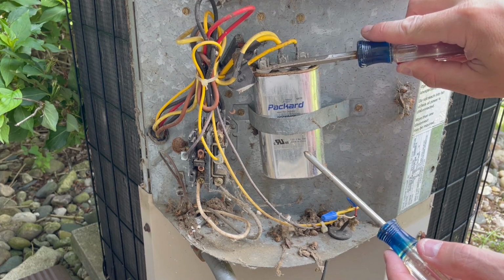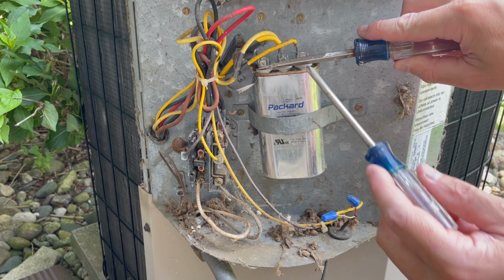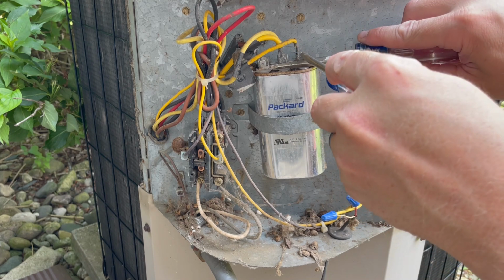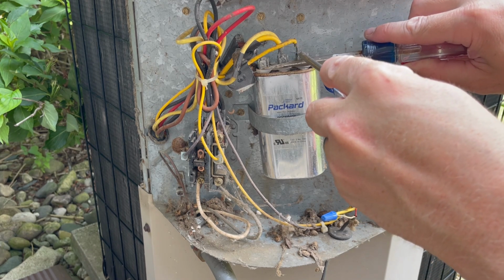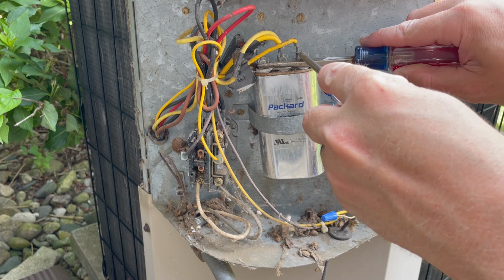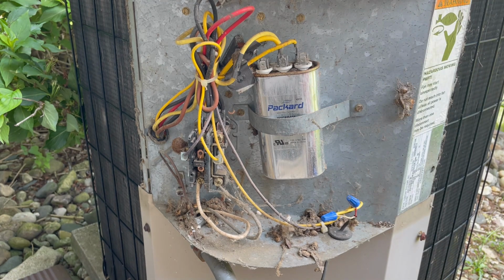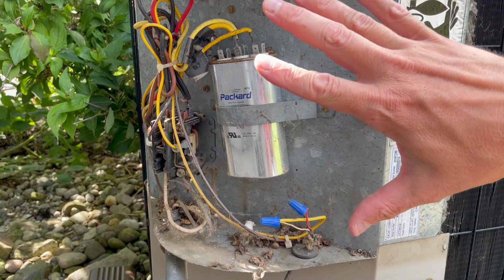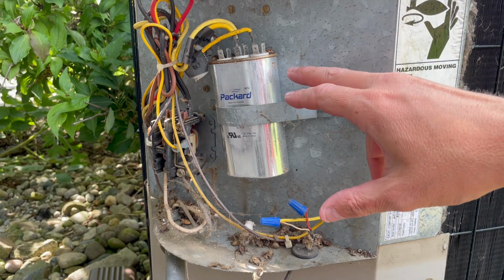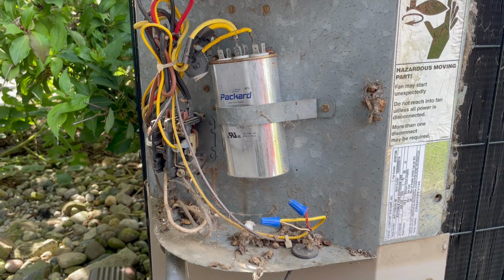So we're going to rub these screwdrivers across the terminals here, and it discharges super quick, so as long as you're touching the terminals, it's almost instantaneous. The buzzing noise we were hearing out here is often a telltale sign that the capacitor may be going bad.